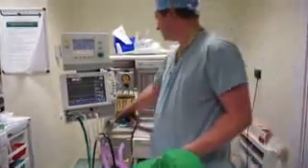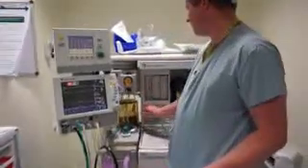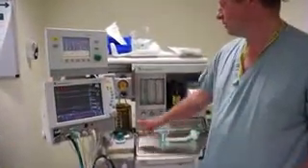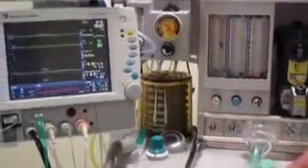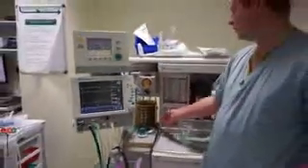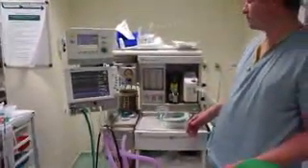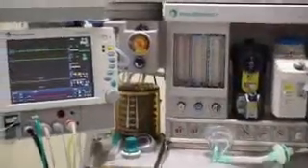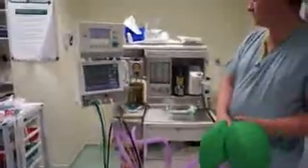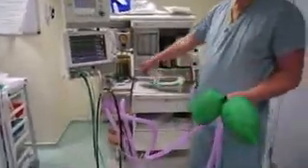Then we're going to check the ventilator. We're going to flip onto the ventilator mode, put a bit of air back into the system, make sure the bellows are fully risen to the top. We'll go for a couple of cycles to make sure there are no major problems, then turn off the flows completely. Watching for the next four or five breath cycles, the bellows should completely fill the bottle again and go right to the top — which it's doing. If there was a slight leak in the system, it won't rise quite to the top and you know you need to hunt around for a leak.